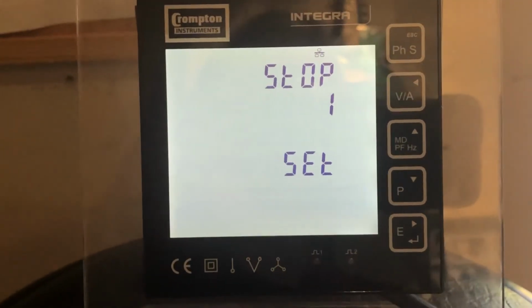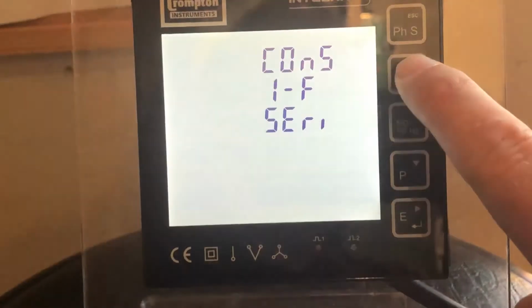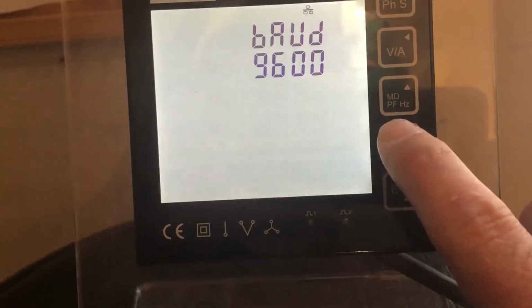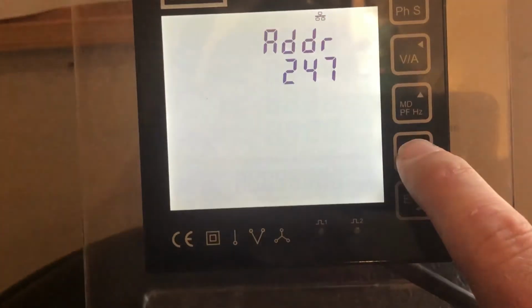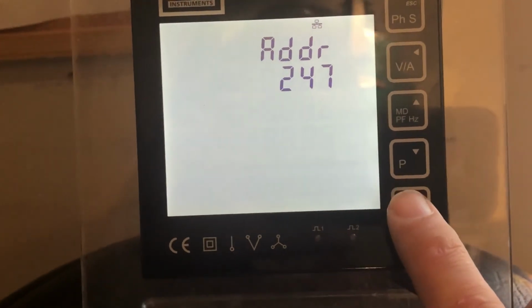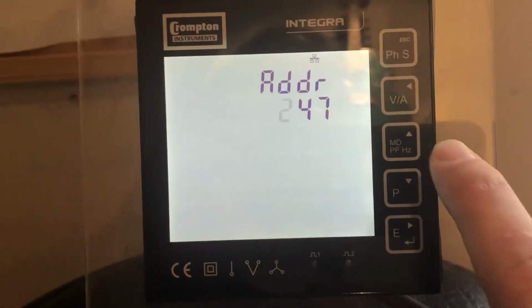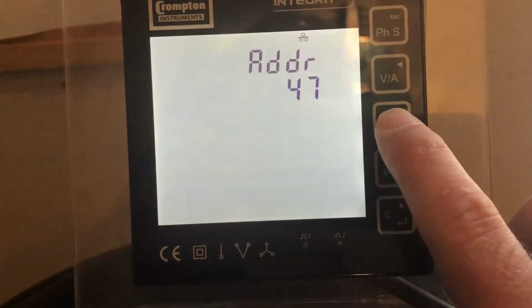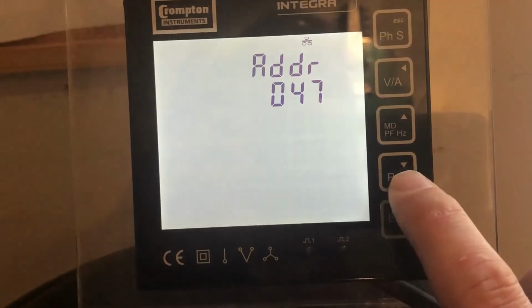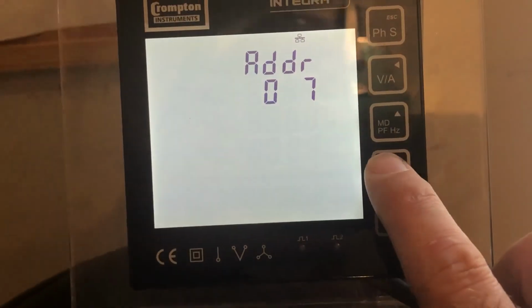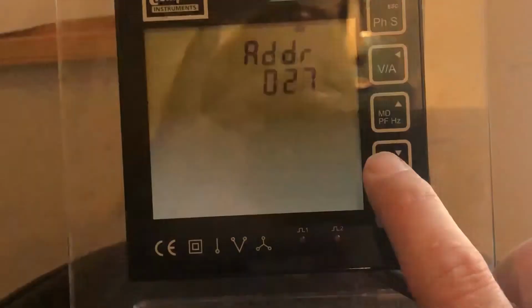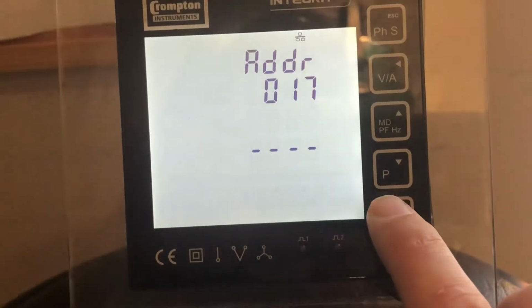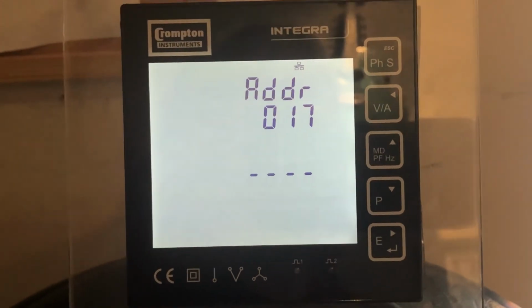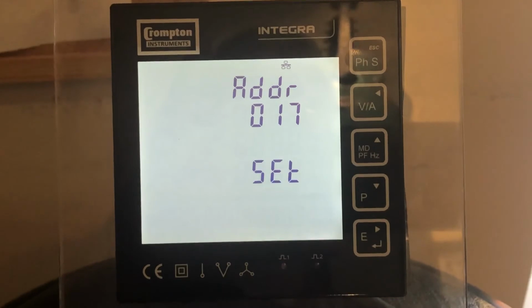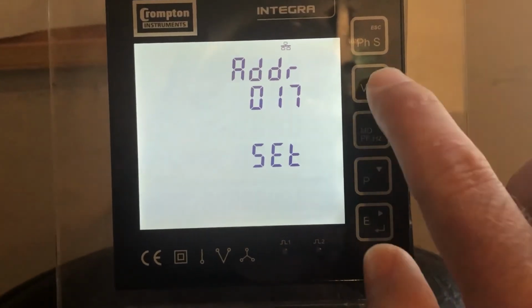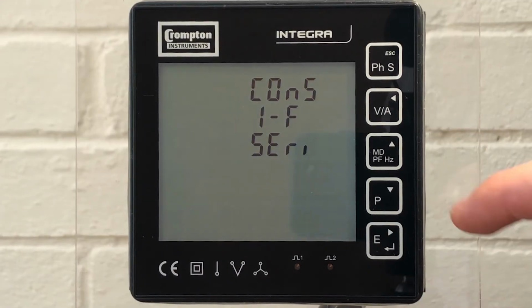Now if we escape out by pressing the VA button, go back into our communications settings, we can set the Modbus node address of the product. At the moment it's set at 247. So we're going to use the arrow up and down buttons and the E button in turn to select our address. I'm going to set this particular meter as address number 17 by holding the E button till it says set. Press the VA button to escape.